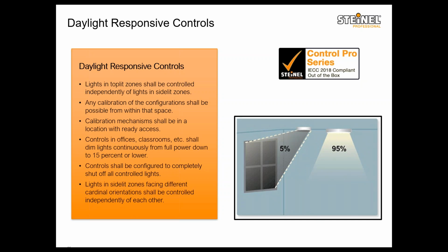And the new topic that has been added is that the lights should be turned off in case the light from outside is exceeding the light level threshold. So you won't have a case of 75-25 anymore if the light level has gone beyond the settings. It would be 100-0.